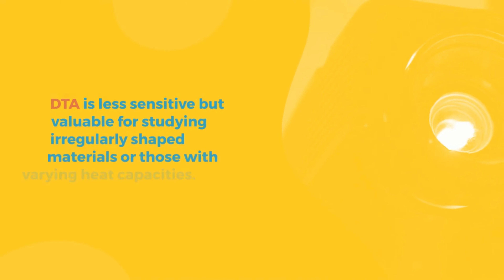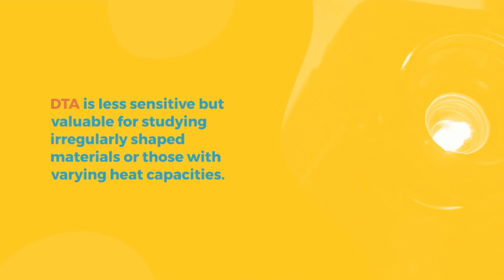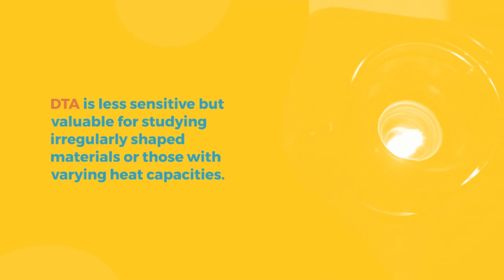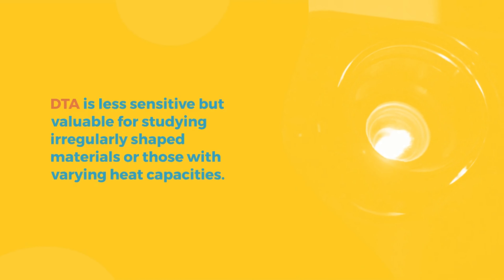DSC is highly sensitive in detecting small energy changes, making it an excellent choice for analyzing minute samples and subtle transitions. DTA, while less sensitive, is valuable for its ability to study materials with irregular shapes or varying heat capacities.